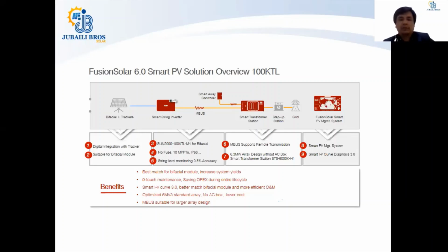So with Huawei, you again have the MBus, which supports remote transmission of the communication data from the inverter to the low voltage side of a transformer. You are usually recommended to use MBus when you are using a smart transformer station, which Huawei can provide. Alternatively, we as Jubaili Bros can also customize the smart transformer station and provide it to you. Huawei has the latest version of IV curve diagnosis now, IV curve diagnosis version 3, which you can use with the new 100 KTL inverter.